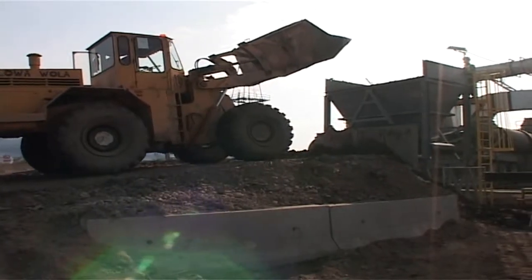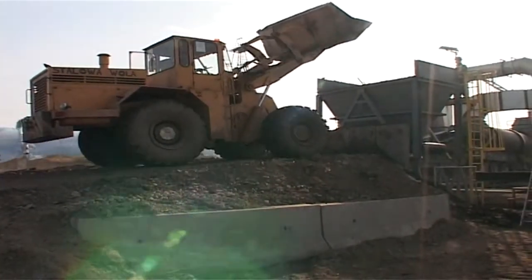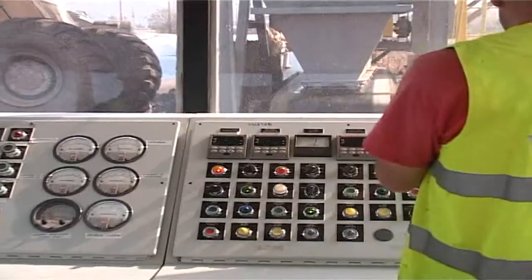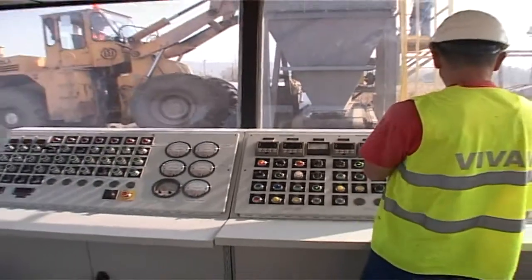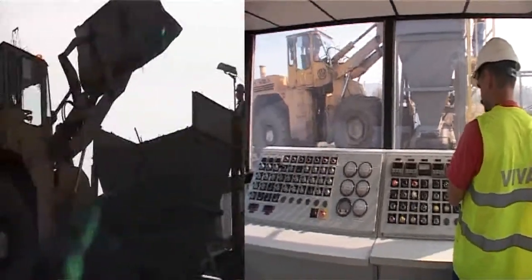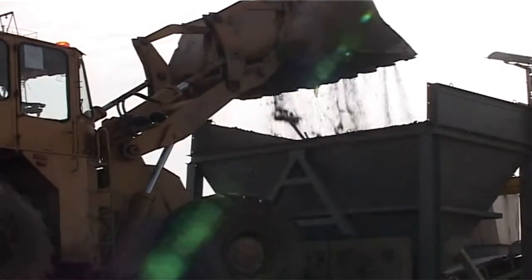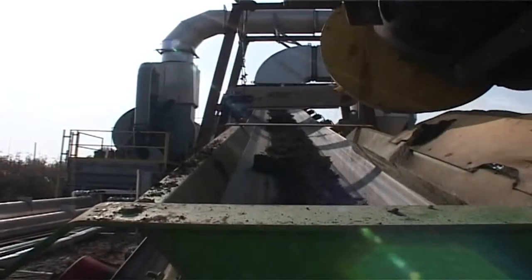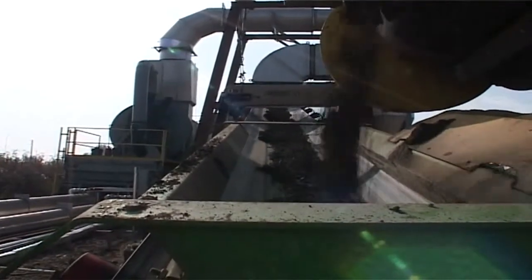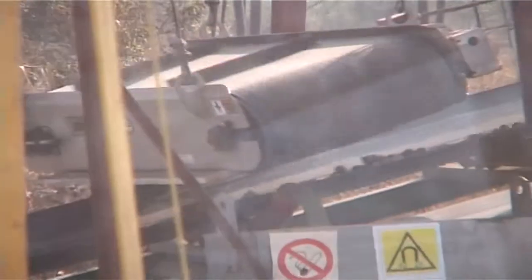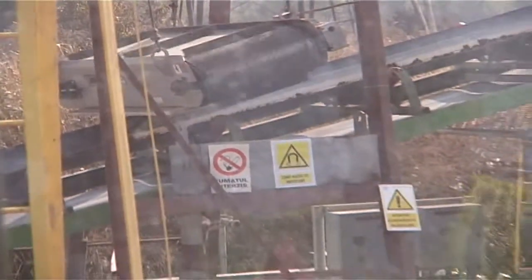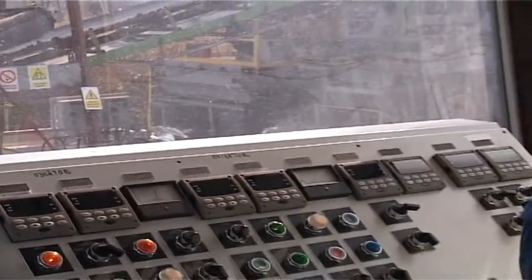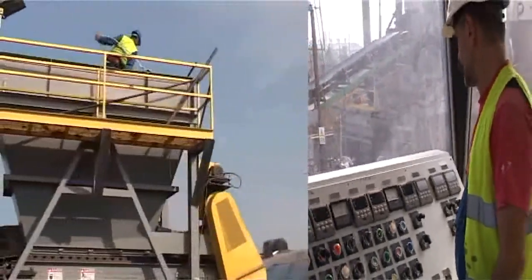First, the sludge is subject to a sorting crushing process performed with a Doppstadt SM 620 screen with 25 tons per hour productivity on a 12.7 mm screen, and that is because there are also other waste substances in the clearing tank, for example rubber, plastic, metal, etc. The sludge is stored on a temporary platform near the clearing cylinder, where it is then fed with the loading machine in the cylinder's feeding funnel.